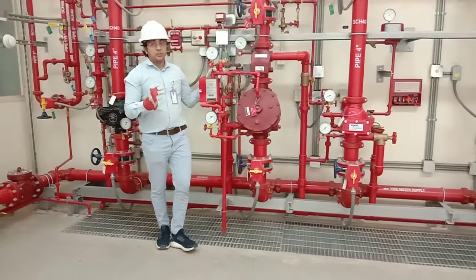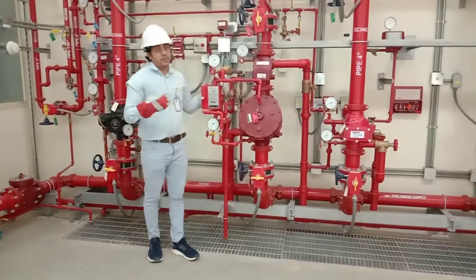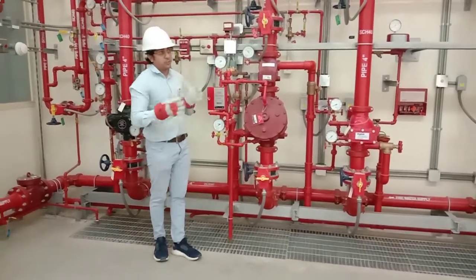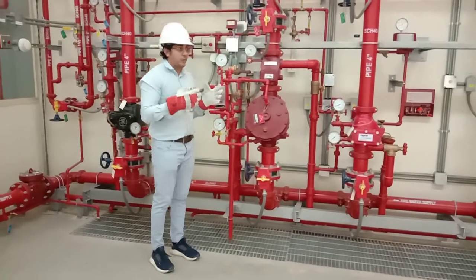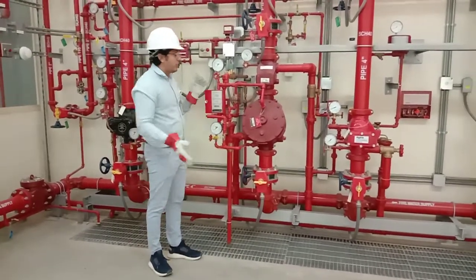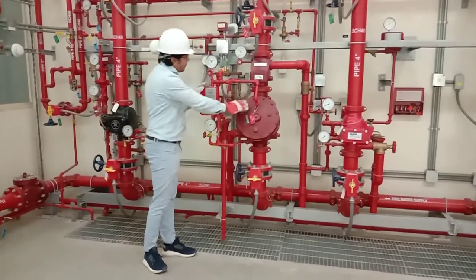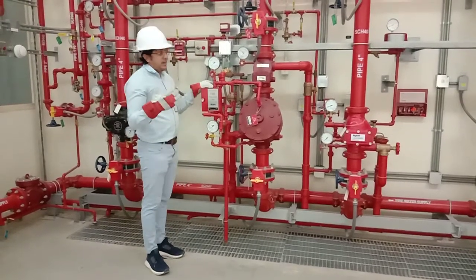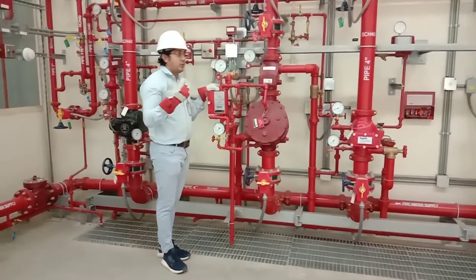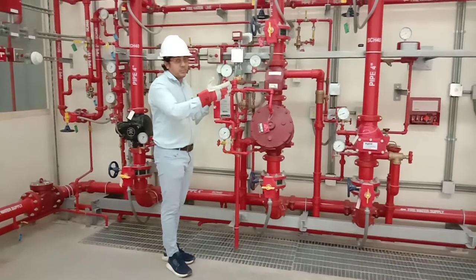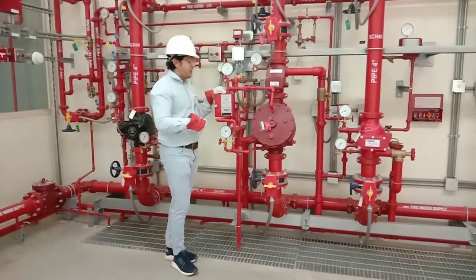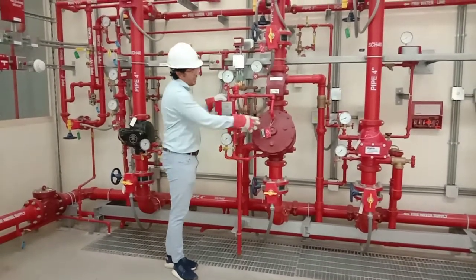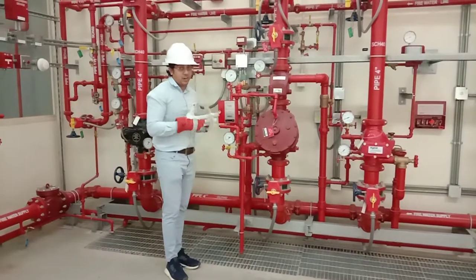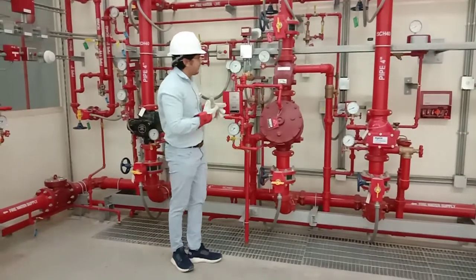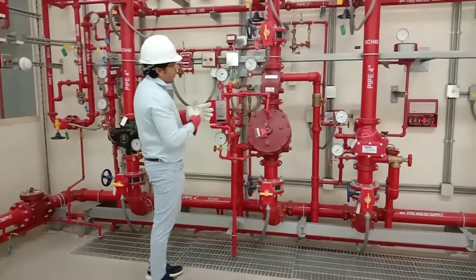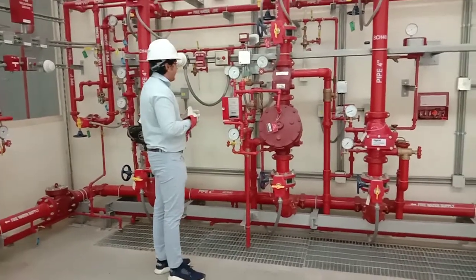Now, what is the meaning of qualified? You have to refer to the NFPA code. They say what is the meaning of qualified: someone who is qualified to do maintenance of a pre-action system. It might be a person who is qualified to do maintenance for the wet pipe system or dry pipe system, but they cannot do maintenance for a pre-action system because, as I said, it's a specialized type of valve and it's heavily protected to avoid the discharge of water mistakenly, right?